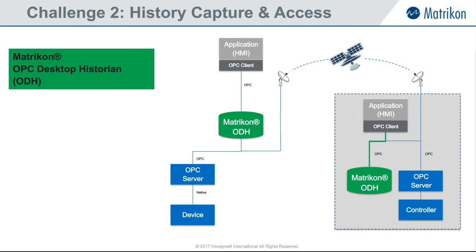So whether you're trying to pull real-time values into it, or you can also extract the values as they come in. So we call that near real-time, because first that has to get captured into ODH, and then its built-in server can expose the data in near real-time. But then, of course, you can also just connect to the source itself if you need pure real-time. On top of that, you would extract the historical data by using OPC HDA. So that's the historical part of the standard, which stands for historical data access.